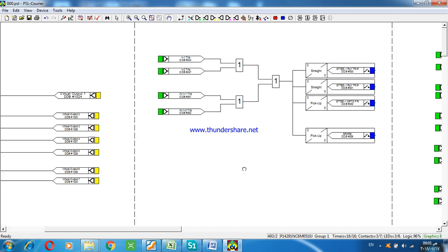Now you have to define all the logic to the relay. If the current is more than 1 ampere, it will consider it overcurrent. Where is that logic? The relay has some settings inside itself.